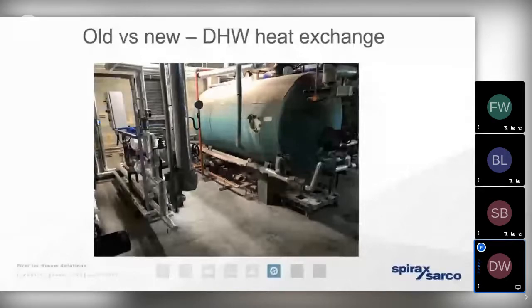Why? Well, we get a very inefficient rate of heat transfer because that A value, the heat transfer surface area, is going to be far, far smaller with a tube bundle assembly than it is with a series of plates. That means if we've got a very, very small A value, we need to have a far, far higher U value to satisfy the rate of heat exchange for the process. That in turn means we're likely to need to condense the steam at a far, far higher pressure. And as we know from referring to the steam tables, the higher the pressure of the steam, the less energy there is present within it, and therefore we get a greater inefficiency.